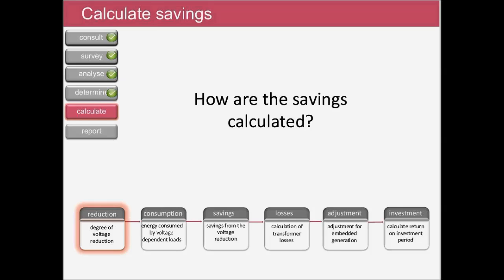So firstly, ascertain the average voltage reduction that the chosen solution will achieve. Then, calculate the proportion of energy consumed by the site's voltage-dependent loads. Calculate the energy savings that the voltage reduction will exhibit. Then, make an adjustment for the losses associated with any voltage management hardware. This may require adding both no load and load losses relating to an additional transformer, or it may require a subtraction of losses as a result of replacing an existing transformer with a low loss or super low loss equivalent.